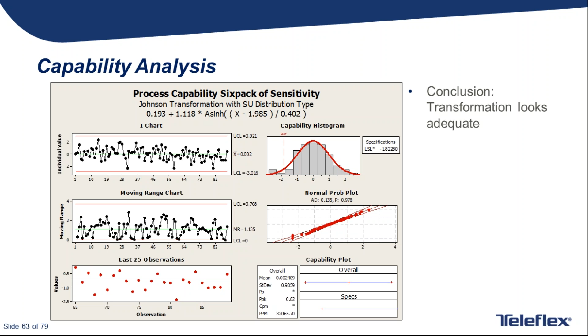With the transformed data, here's what the tolerance interval analysis looked like. The output showed that with 95% confidence, more than 90% of the data was above the acceptance criteria. Therefore, despite initial discouragement at the failed attribute analysis, this more detailed variable analysis demonstrated that the data did actually meet risk-based acceptance criteria, and at a higher level than the original attribute testing acceptance criteria was.